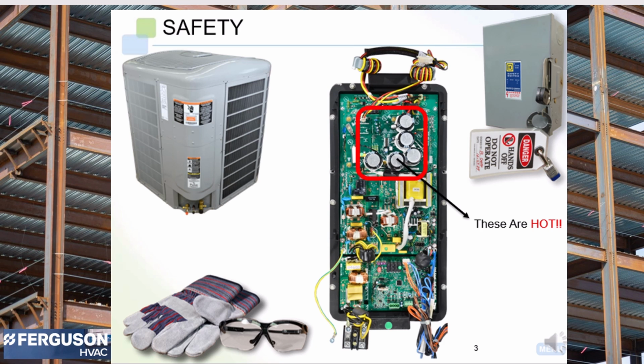Anytime you are working around inverter equipment, you must practice all safety procedures. The capacitors on an inverter hold a very high DC voltage charge. Always make sure the system is properly locked out and you have the appropriate PPE gear before working on an inverter. Always be safe out there.